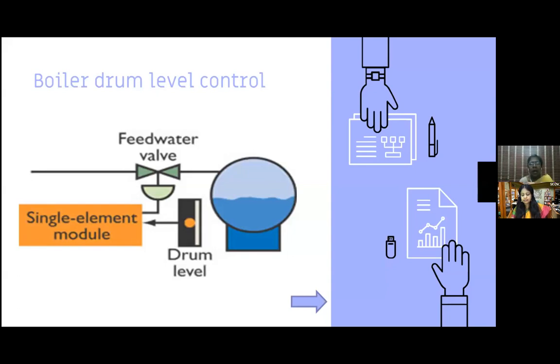The level sensor, along with the signal conditioning and range conversion circuit, is what we call a level transmitter. The transmitter gives me the change in level in terms of current, and I receive the signal and compare it with the reference value. Let us assume the value I'm receiving is 25 meter, while the reference value is 20 meter. That is, I want to maintain 20 meter level in a boiler, but actually it is 25.